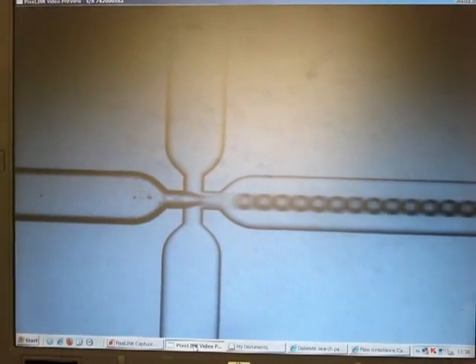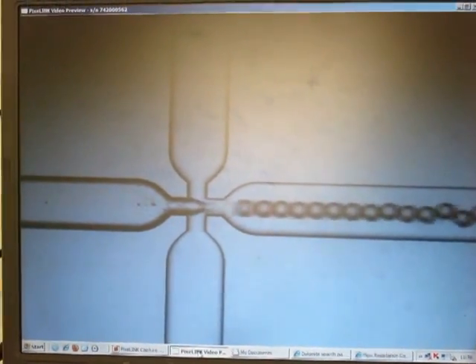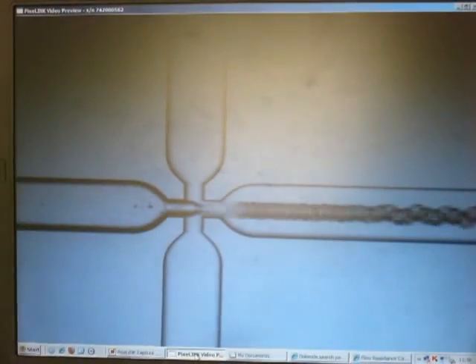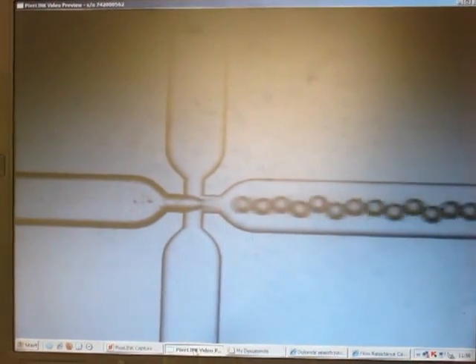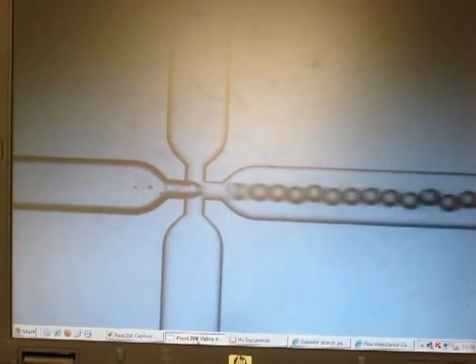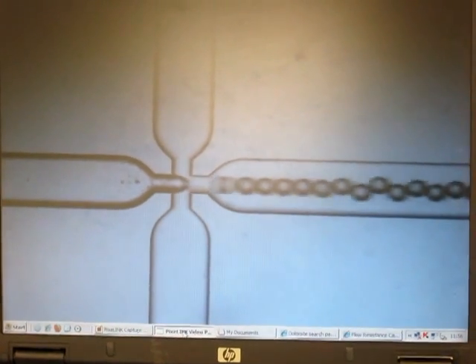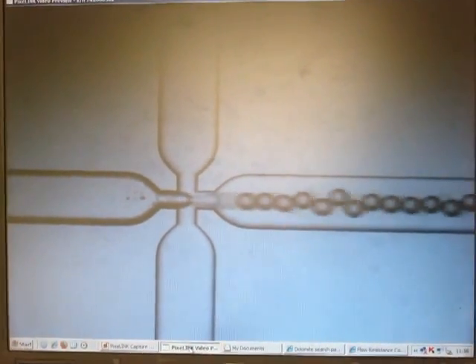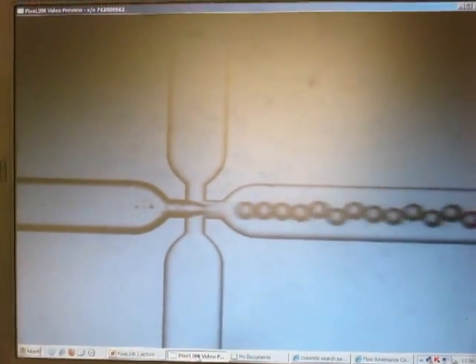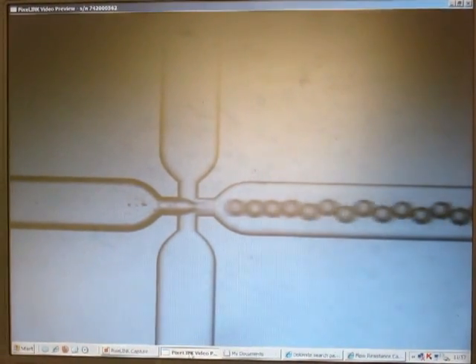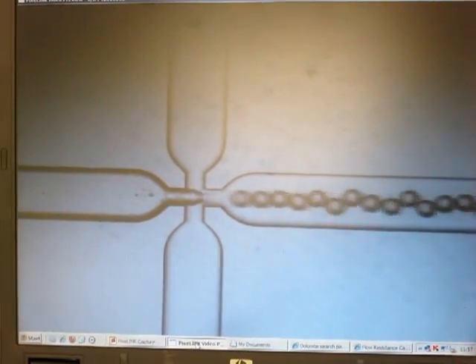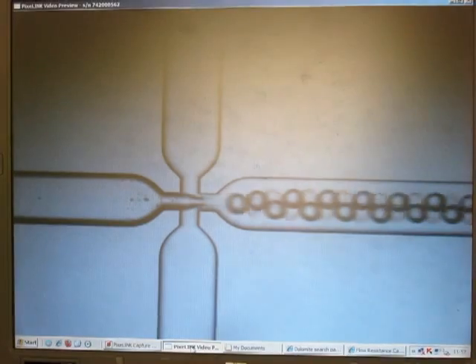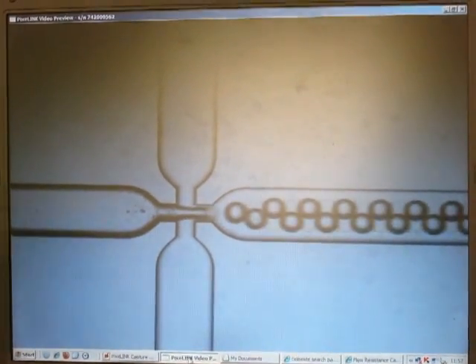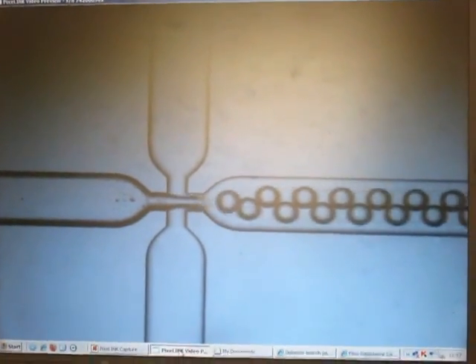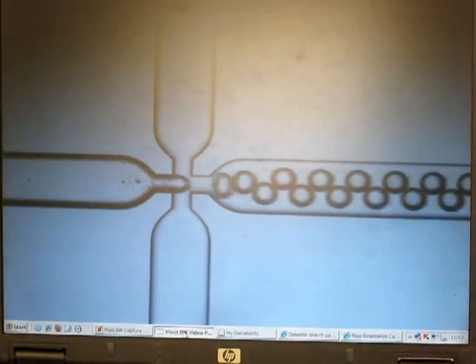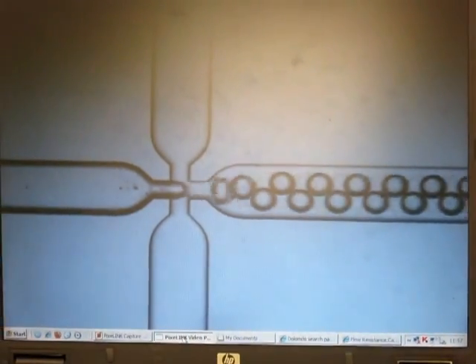Okay, so the droplets are about 100 microns in size now, and you can see they're starting to bunch a little bit. I'll go down again, I'll reduce the oil flow rate by half again. Okay, so you can see the droplets have now increased. The droplet size is around 150 microns, and they're starting to bunch up a little bit there in the chip.